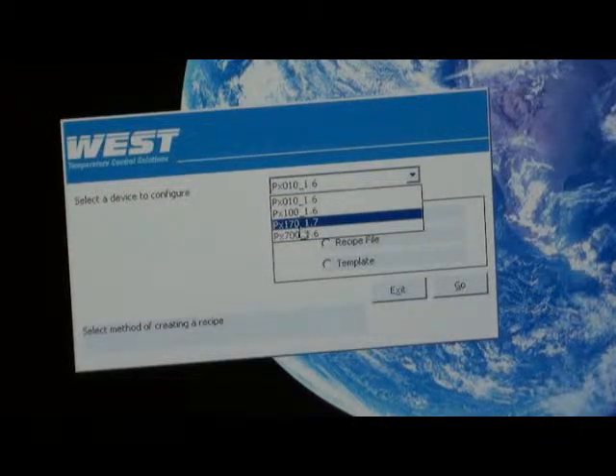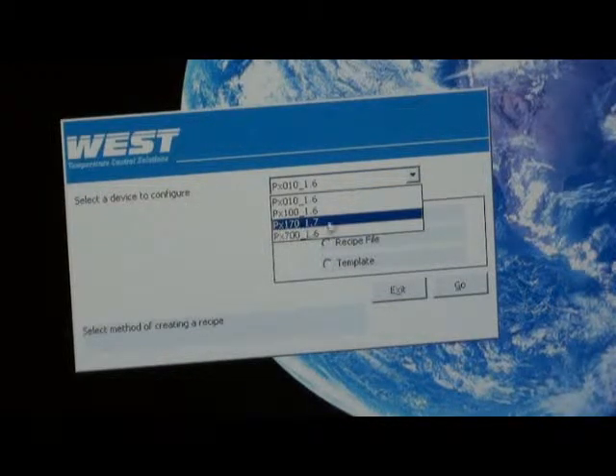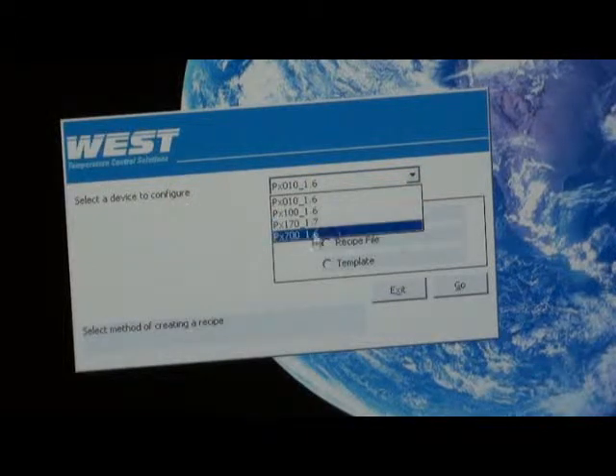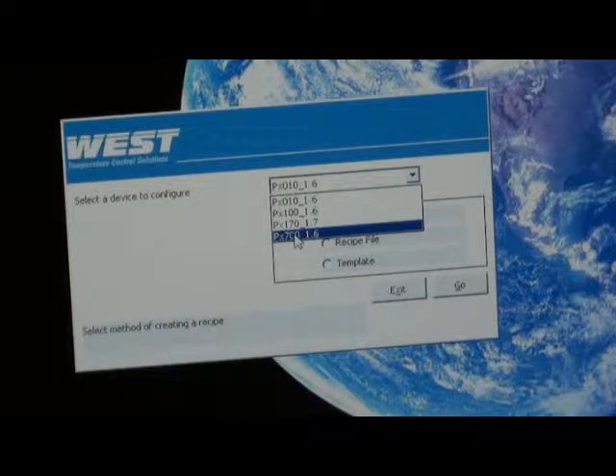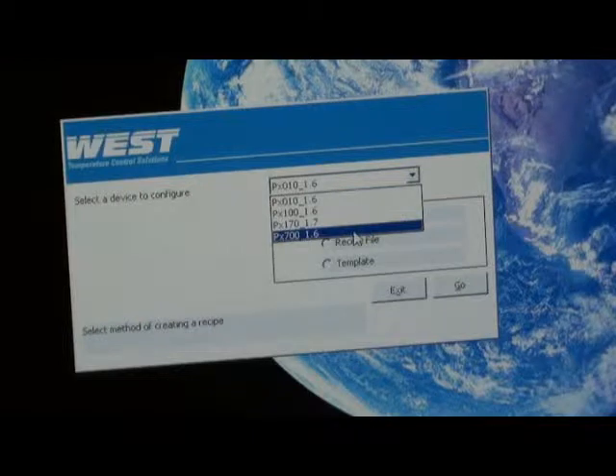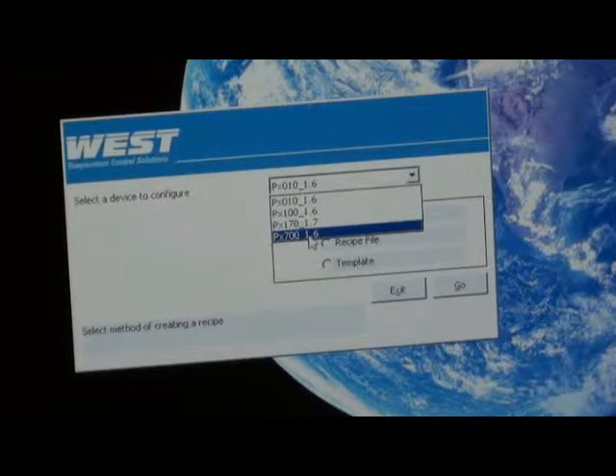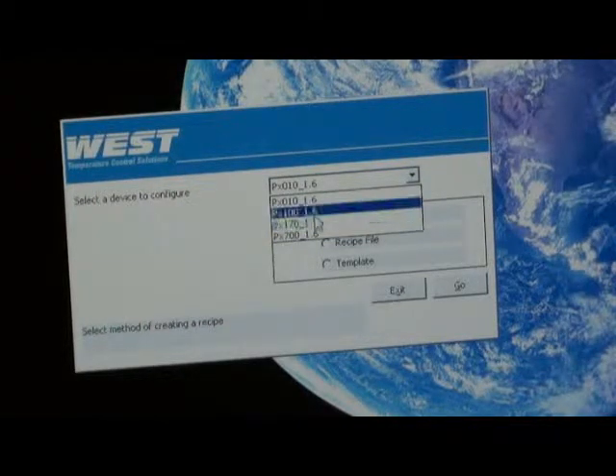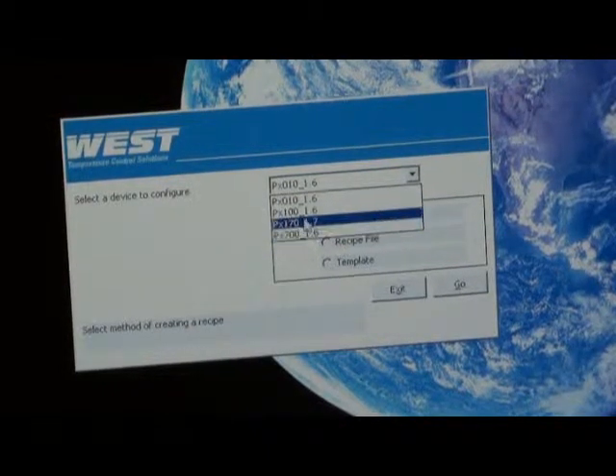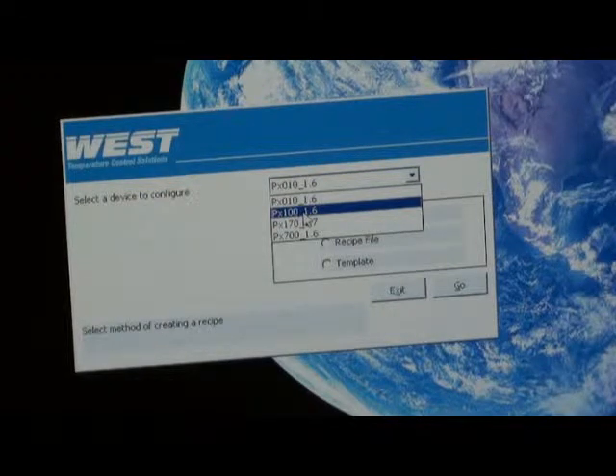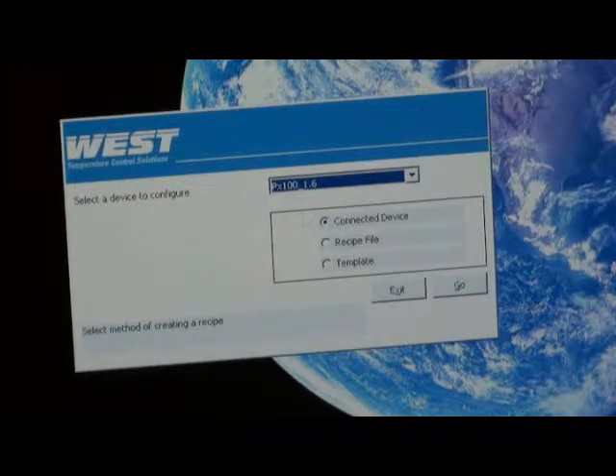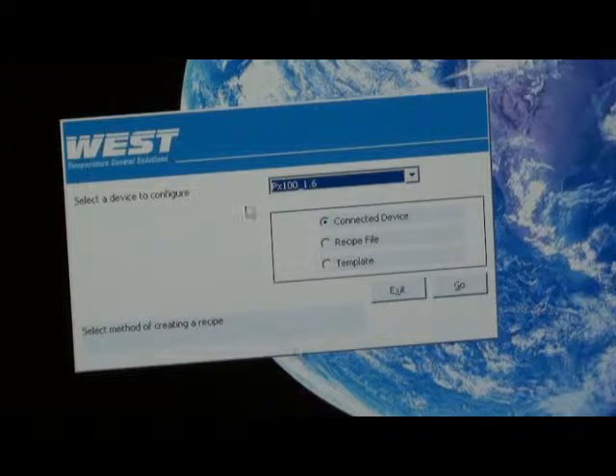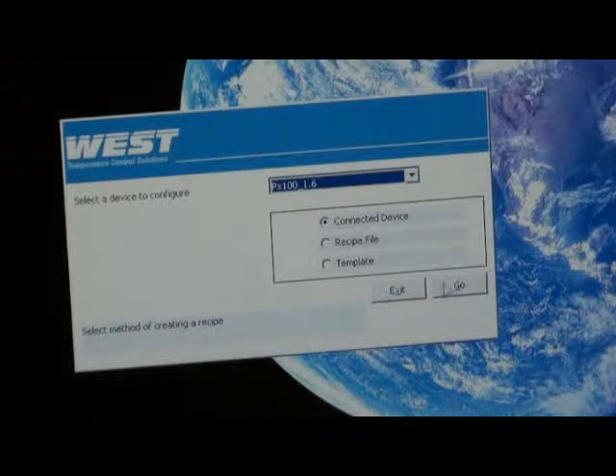Here would be the 6D170 or 8170, the valve motor drive controllers, and the P4700 or 6D700 or 8700 limit alarm units. So it's very important, right from the beginning, to choose the correct controller or indicator that you want to program. We will need to select the P6100 because we're going to configure a P6100 controller. On the menu we've got P6100, go to Connected Device, go.